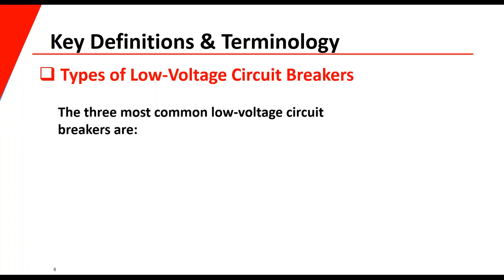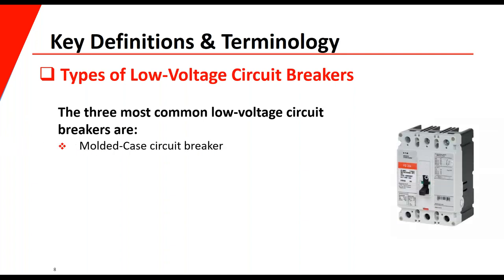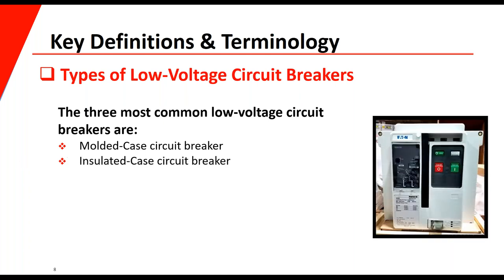The types of low voltage circuit breakers — the three most common you're going to see are: the molded case breaker, which we're not really going to cover today but they do have their own tripping features; the insulated case circuit breakers, which are difficult to distinguish from molded case breakers, but use solid state trip devices; and the air power circuit breakers. Insulated case breakers are a step up from molded case breakers, even though they're made to the same standard.